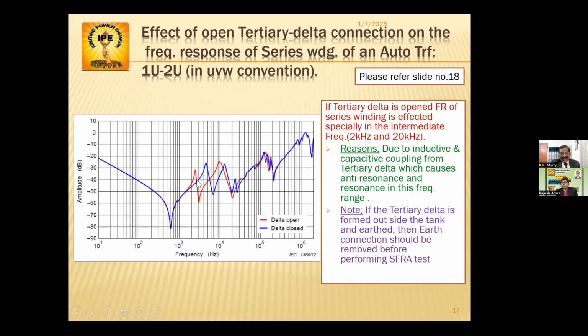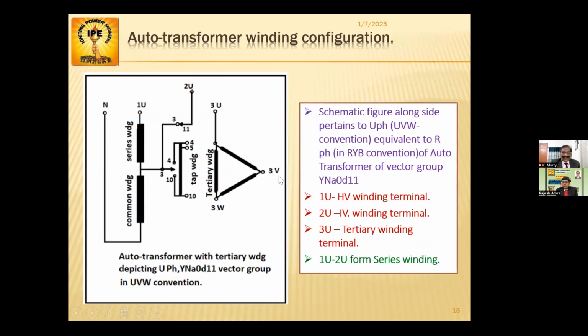You can see this red curve of open delta when the delta is opened and tested. The reason is inductive and capacitive coupling from the tertiary delta, which causes anti-resonance and resonance in this frequency range, with the series winding. And what is series winding?